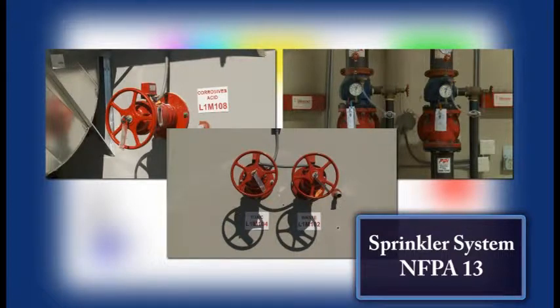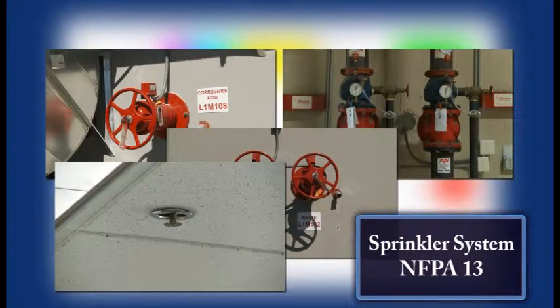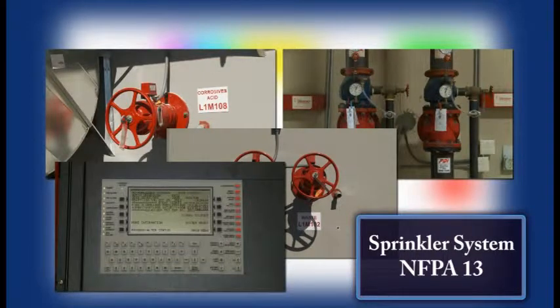Tamper and flow zone isolation valves are located in or adjacent to each of the areas served by the wet pipe sprinkler system. Failure of the heat sensing element at any sprinkler head will result in immediate sprinkler operation in the affected area. Water flow within an individual zone will initiate a fire alarm via the fire detection and alarm system. The main sprinkler system and riser valves are provided with automatic monitoring of pressure, tamper, and flow status at the zone valve assembly. If the tamper switch at any system component is activated, or if the low water pressure switch is activated, this signal will cause a trouble condition on the fire alarm control panel, and its identification will be annunciated.